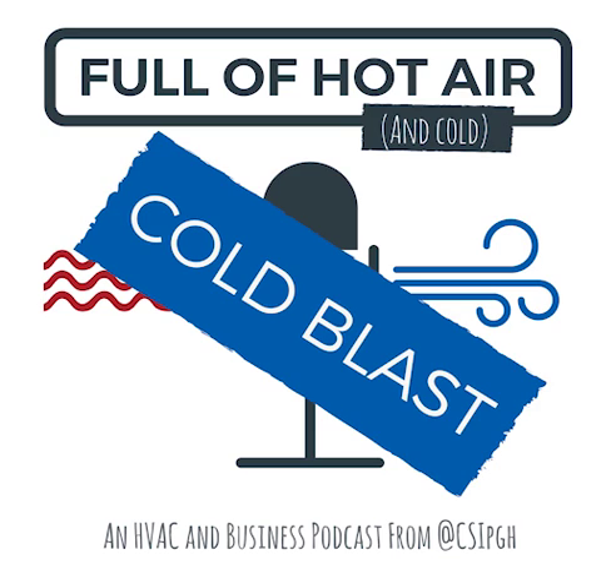Now the other formula would be if you have an air handler. It's not a gas furnace, it's an air handler, so I've got kilowatts and not BTUs. Same formula, same idea, but now we take what our electric heaters are. Let's say we have a 15 kW heater setup. Since there's a variable of your incoming voltage, L1, L2, it doesn't mean it's always going to output the same. The lower the voltage, the lower the output. The higher the voltage, the higher the output.